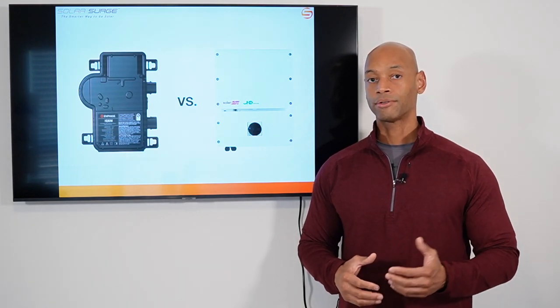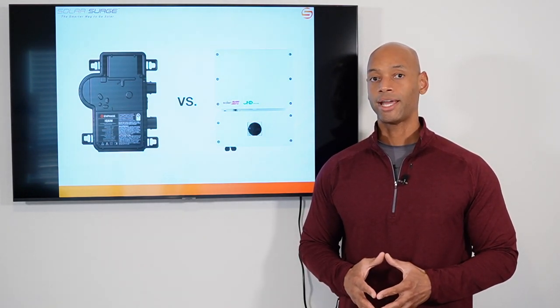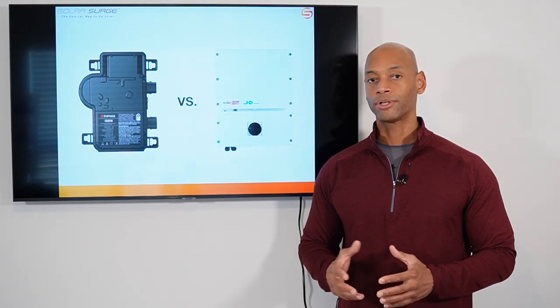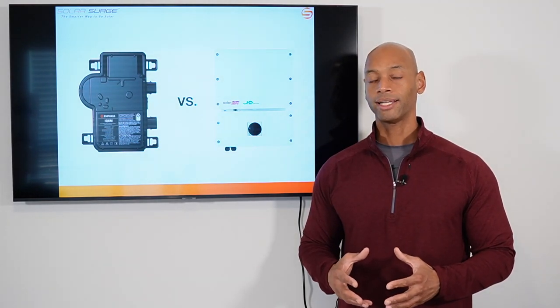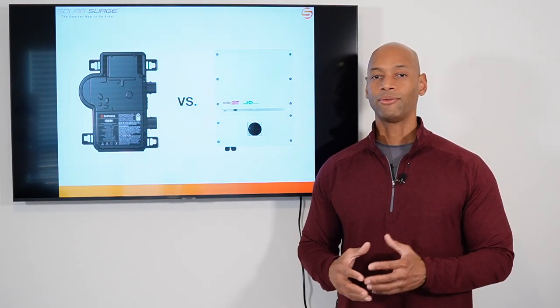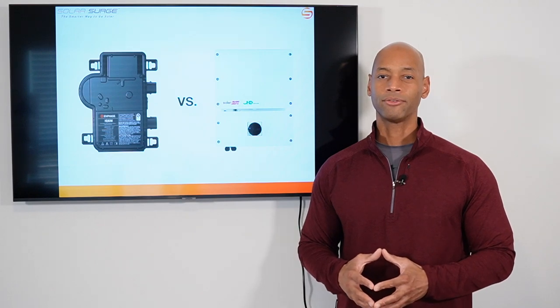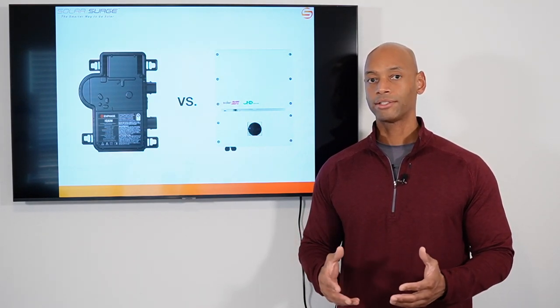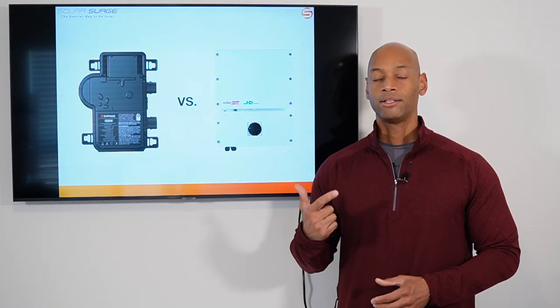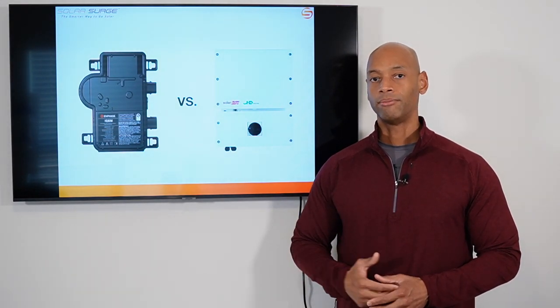And so even now, as of this recording, even with the current generation Enphase microinverters, you're limited to between 11 and 14 microinverters per trunking cable. So you have to set up a separate cable and the wiring is a little bit more cumbersome on the roof. But all in all it was a great solution, solved the single point of failure problem, solved the module level monitoring problem.